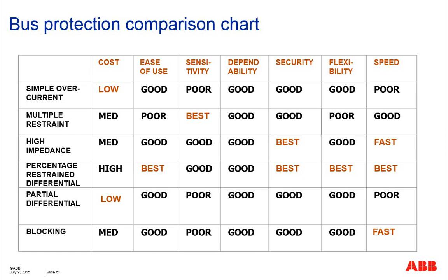The migration is progressing towards the low impedance approach. You don't really see a lot of high impedance relays anymore. At least in my area, most of the old high impedance busbar protection has been updated, retrofitted with modern numerical low impedance busbar protection relays, because they can offer the same sensitivity and security, thanks to the internal algorithms to overcome CT saturation and even CT opening and closing.